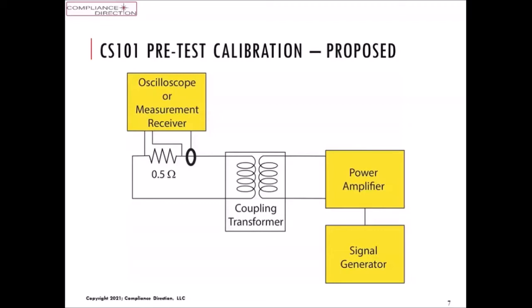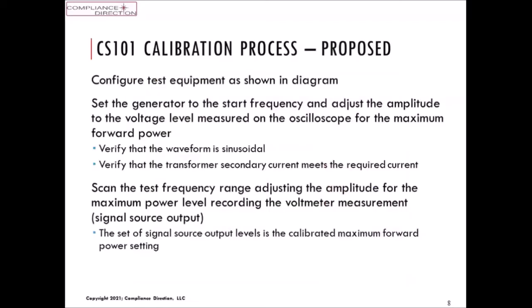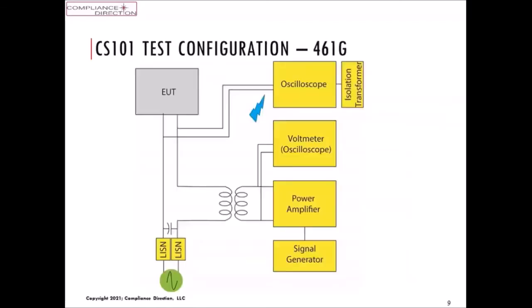And the reason for doing that is to ensure that I'm not overdriving the power amplifier, causing a lot of distortion. So we're operating the power amplifier system in the linear region. A good power amplifier tolerates that pretty well, but we've got quite a few that get spec'd into the laboratory that may not be so responsive. So we need to validate that on an as-needed basis, plus make sure nothing has deteriorated. And that's what these words basically say. It's right there in case you have the slide.